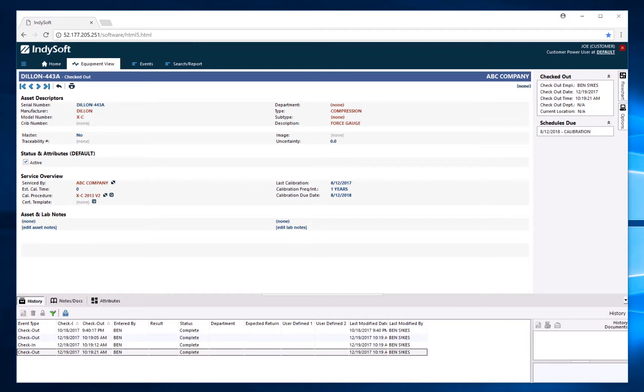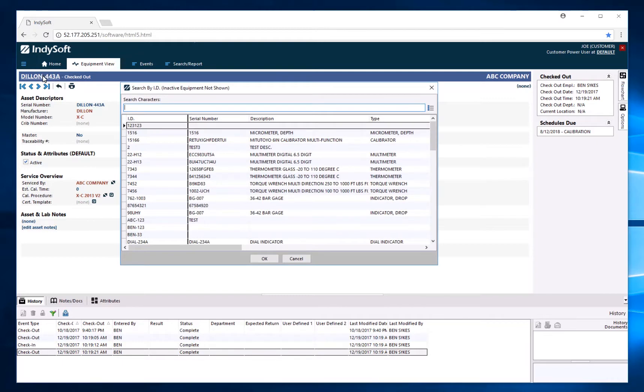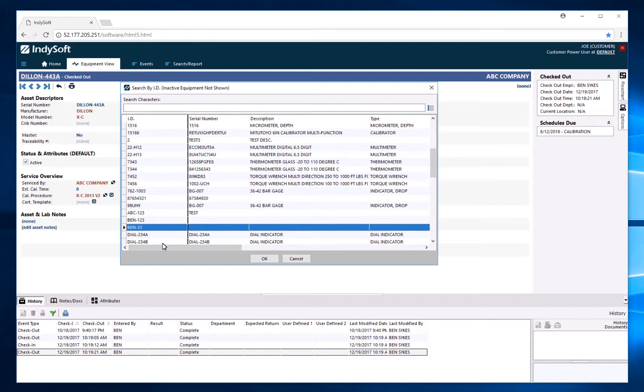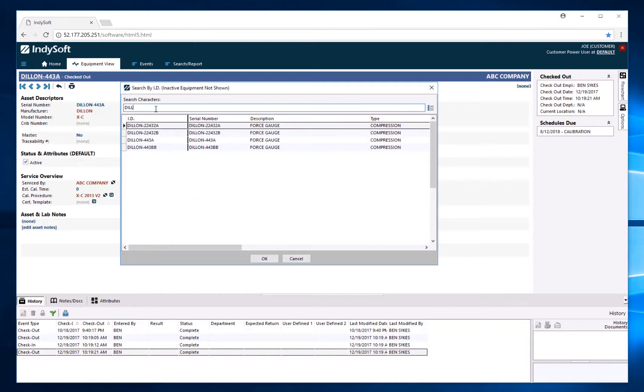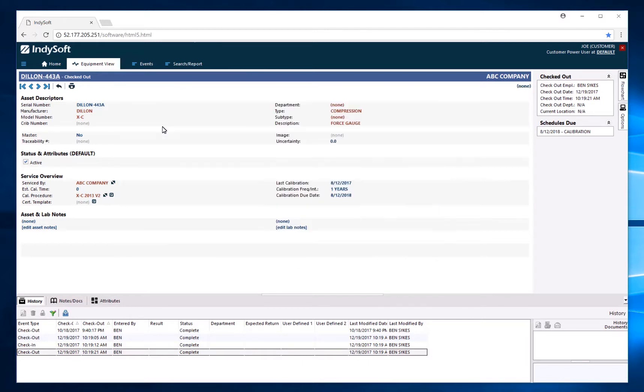We also have asset and lab notes. In the upper right-hand corner we have the tracking status and its associated information, and you can also see the calibration schedule here. The ID in the upper left-hand corner also functions as a quick search — if we click on it, a search menu appears where we can find different assets. Let's target an asset with a calibration applied to it — I'll pick this force gauge and double click on it.